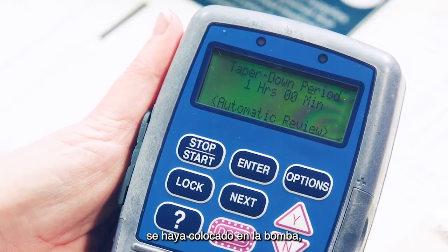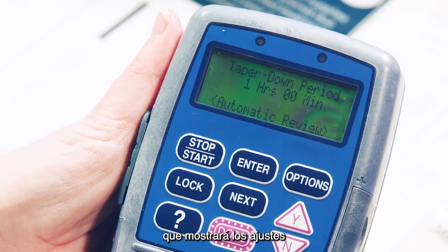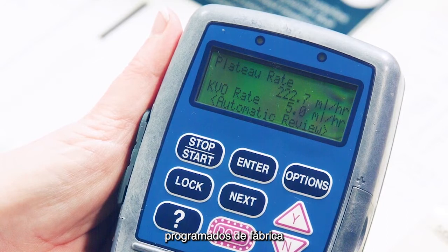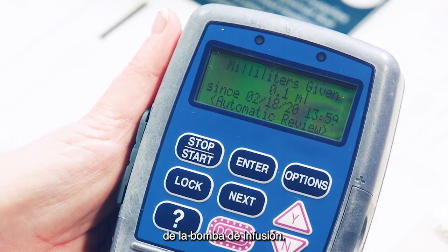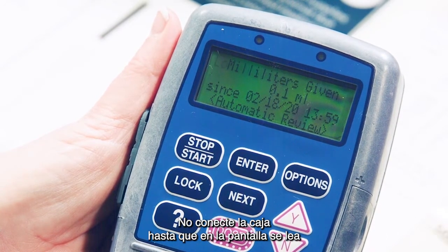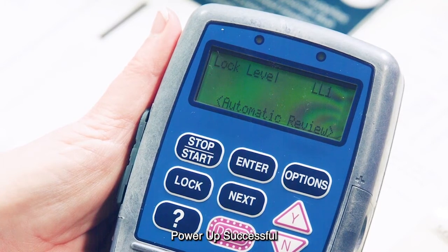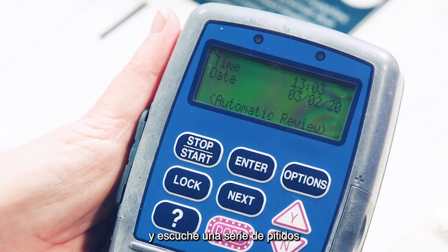Once the battery has been placed into the pump, it will go through an automatic review displaying the pre-programmed pump infusion settings. Do not attach cassette until screen reads Power Up Successful and you hear a series of beeps.